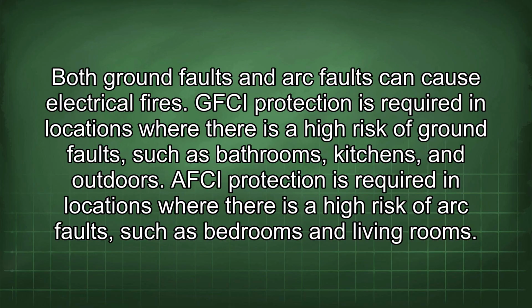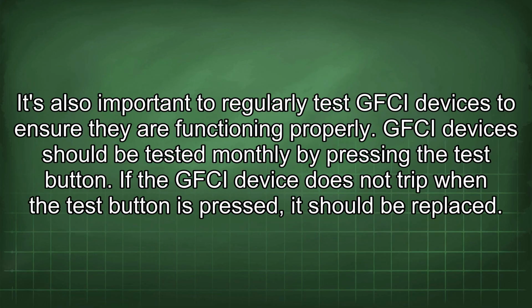GFCI protection is required in locations where there is a high risk of ground faults, such as bathrooms, kitchens, and outdoors. AFCI protection is required in locations where there is a high risk of arc faults, such as bedrooms and living rooms. It's also important to regularly test GFCI devices to ensure they are functioning properly. GFCI devices should be tested monthly by pressing the test button. If the GFCI device does not trip when the test button is pressed, it should be replaced.